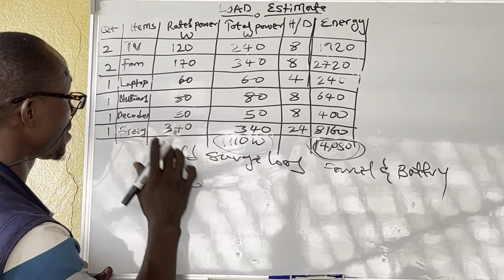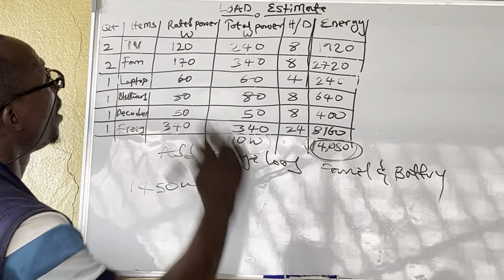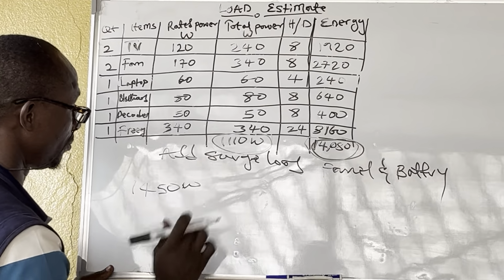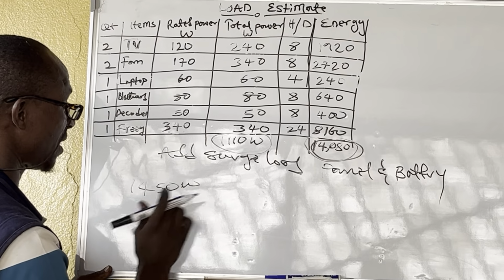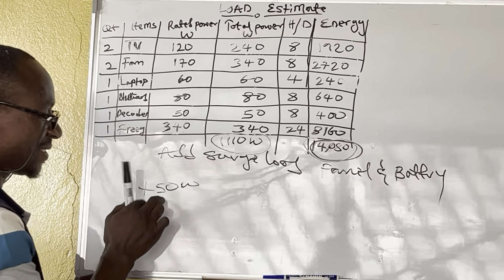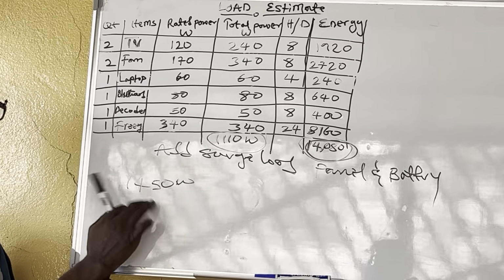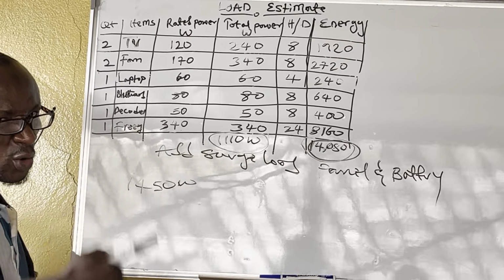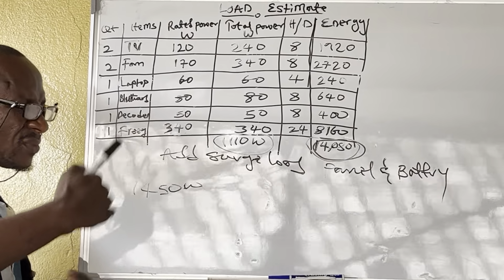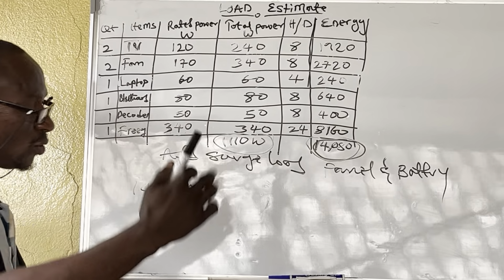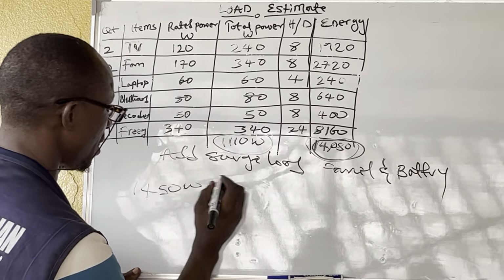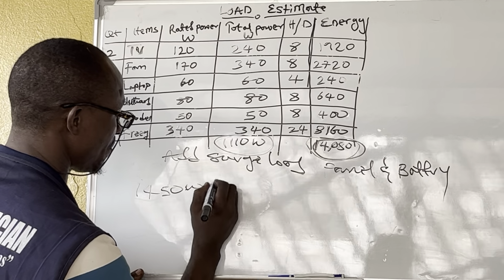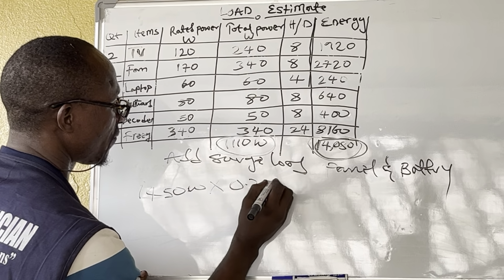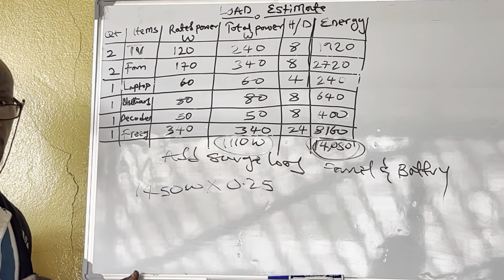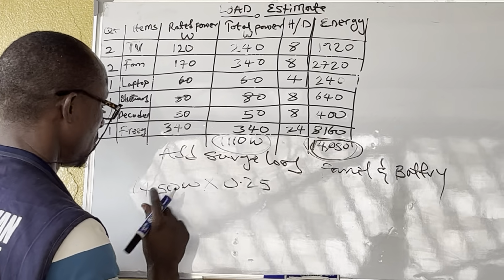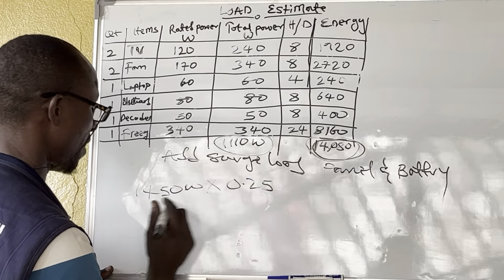So to calculate our rated power to size our inverter, we are going to look for 25% load estimate, as in future load, 25% future load. So we say 1,450 times 0.25. Please check: 1,450 times 0.25.